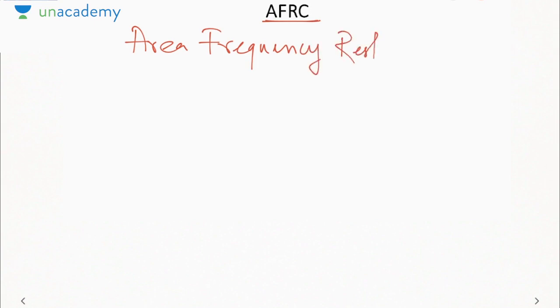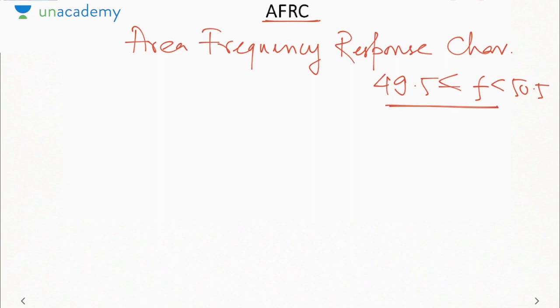Now let us understand some terms associated with this frequency control. First is AFRC. It is area frequency response characteristics. Okay, that is AFRC, area frequency response characteristics. Now what do they show is, in a power system area, how does the frequency vary with change in load? Because you might have implemented some frequency control method, let us say flat tie line control. Then I must know if by changing the load how much the frequency deviates, so that I know what maximum load can be connected in a system, as the frequency must always remain between 49.5 Hz to 50.5 Hz. Okay, so if I know the AFRC, then I will know how much loading can be there in the system.